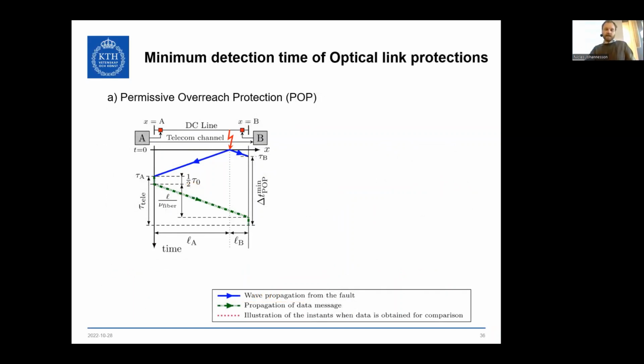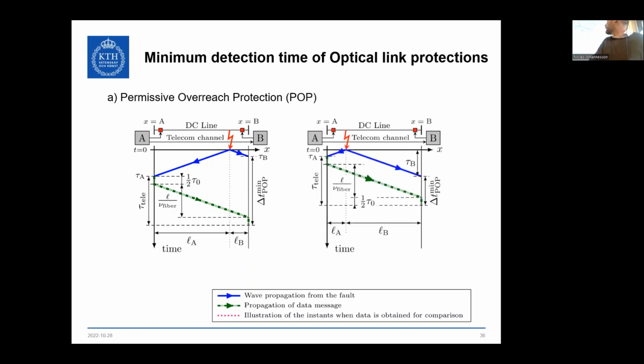This is the wave propagation and communication path during an internal fault. You have a fault fairly close to terminal B, which launches waves going in both directions, arriving at tau B and tau A. The detection time in this case requires the protection to first detect it at B, then at A, and that detection from A needs to travel to B, giving a very long time delay. However, in the opposite direction, if the fault is very far away, you get a much smaller time delay.